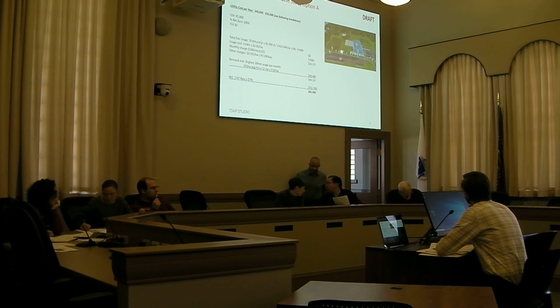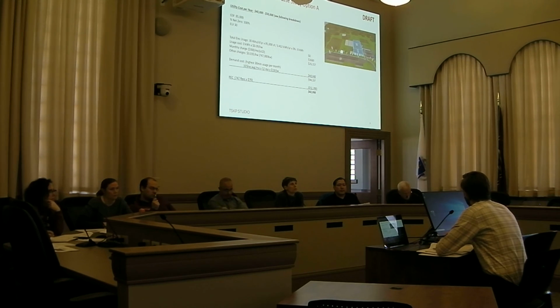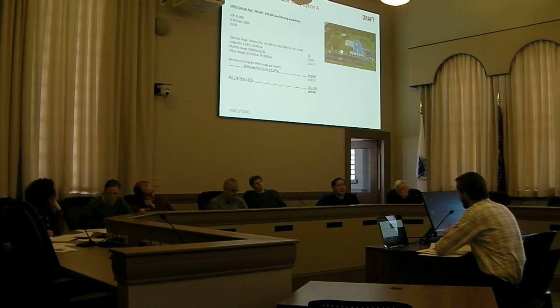And the peak demand again is winter or summer school use? Well, it's the peak demand each month, the top 30 minutes each month. So it makes it hard to think about, because normally in the past, we've always thought about peak demand year-round, and then you end up in the summer usually, which we already talked about a little in the previous meeting. But here we're talking about the peak demand each month, so it's 12 different peaks. We use the energy model to try to predict that as best we could.